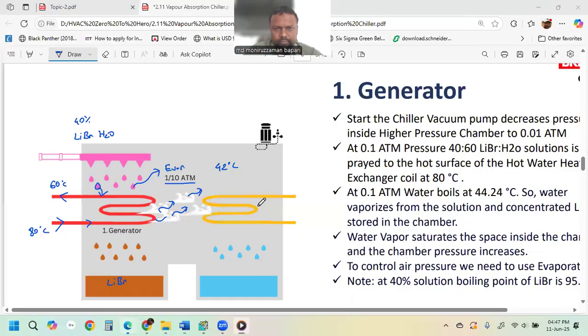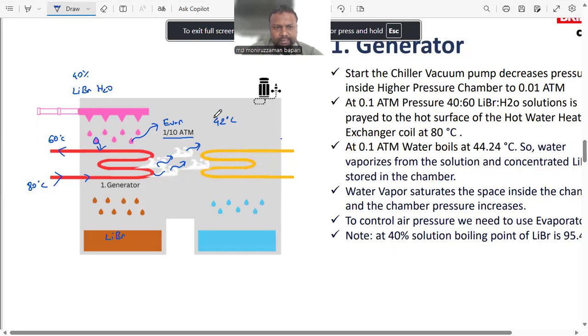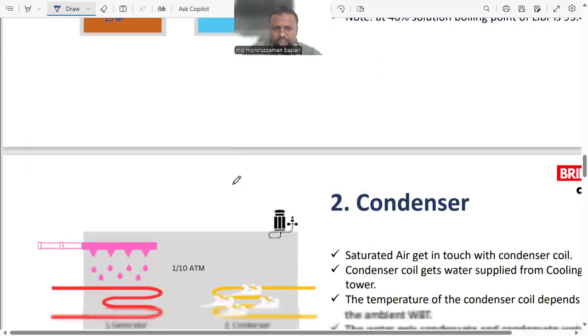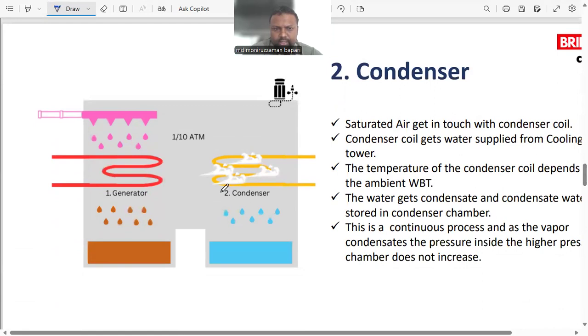Moving on, for now, after generation, inside the higher pressure chamber, pressure is supposed to go high because the vapor already filled the whole area. Now we need to remove this vapor. And how to do so? We do it by condensation. So the second stage is the condenser. Through the condenser, comparatively cold water passes from the cooling tower, and condensation happens. So whatever vapor is generated in generation is condensed and stored in a pan in here. The second step, condenser.